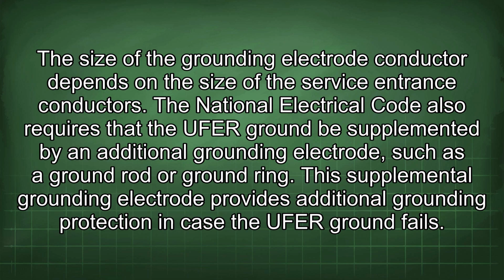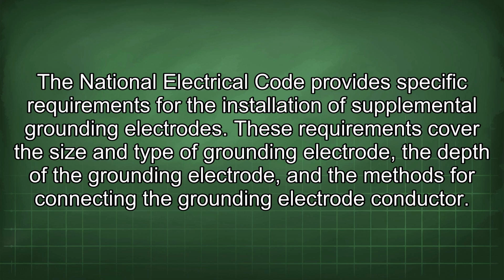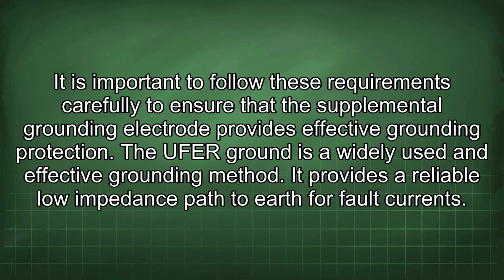The National Electrical Code also requires that the UFER ground be supplemented by an additional grounding electrode, such as a ground rod or ground ring. This supplemental grounding electrode provides additional grounding protection in case the UFER ground fails. The National Electrical Code provides specific requirements for the installation of supplemental grounding electrodes. These requirements cover the size and type of grounding electrode, the depth of the grounding electrode, and the methods for connecting the grounding electrode conductor. It is important to follow these requirements carefully to ensure that the supplemental grounding electrode provides effective grounding protection.